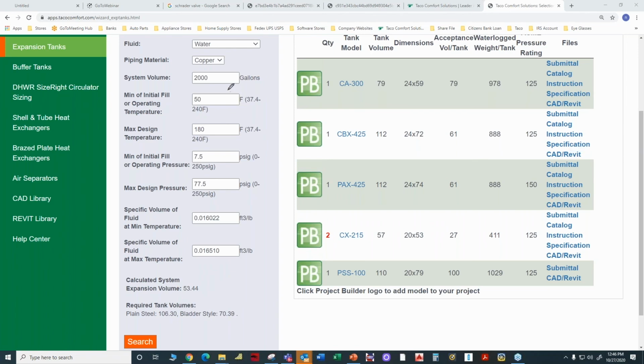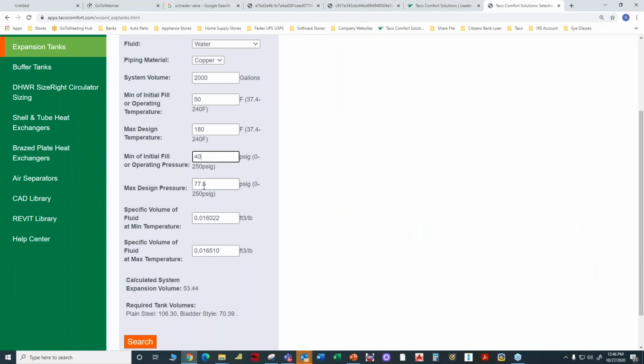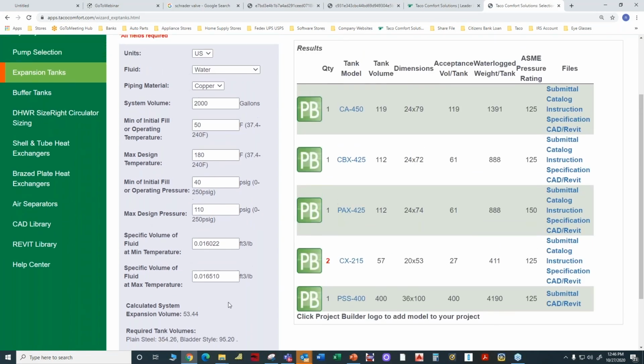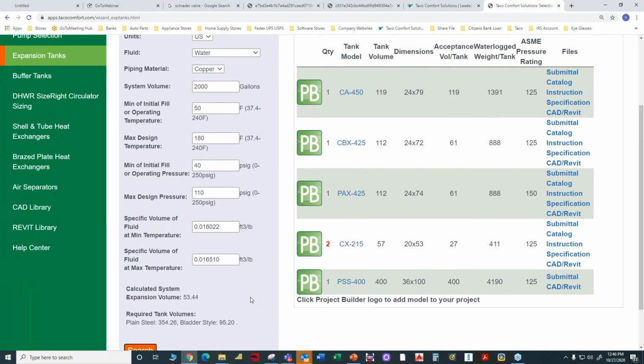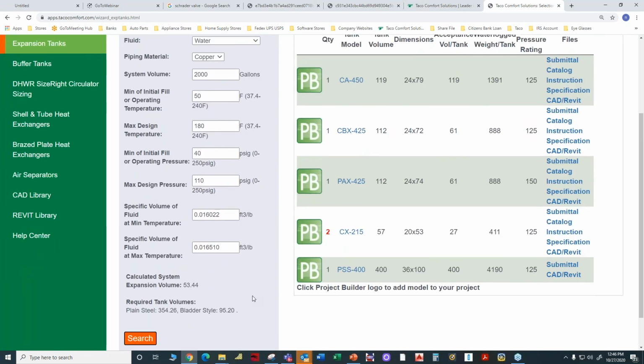Let's go back to our original criteria of 40 pounds and 110 pounds, going back to our original example. Now, let's assume we have this project, and I've shown you the diagram, and the selection was based on water. This happens periodically. We'll get a call at the office back in Cranston, and someone says, hey, look, I selected an expansion tank. I hooked it all up. I did everything I was supposed to do, but the safety relief valve keeps going off. Well, what's going on? What's wrong with your tank?